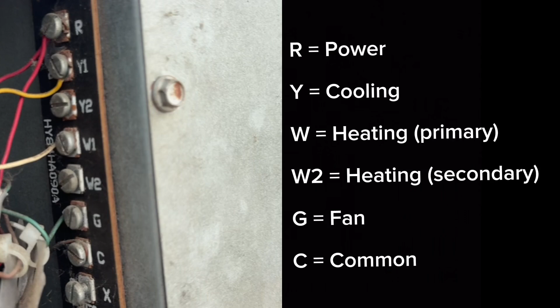I'll show a graphic of each of them, but first thing is to check power to 24, so the R, with your meter. For this scenario, I was not getting any 24 volt power.